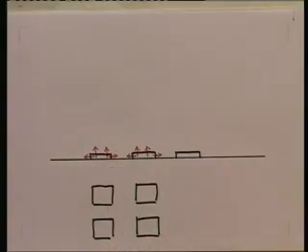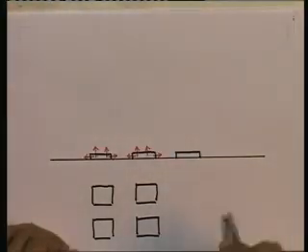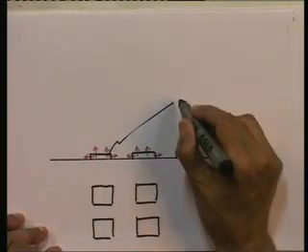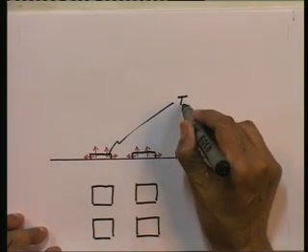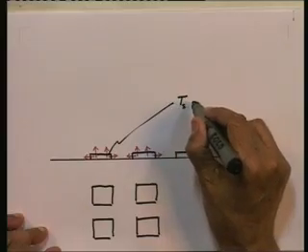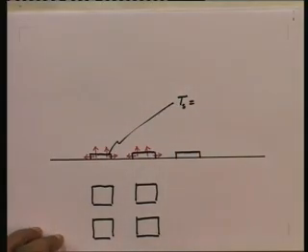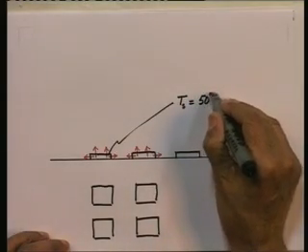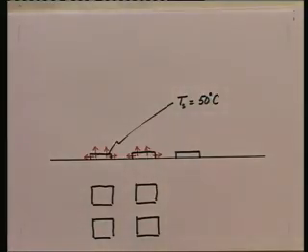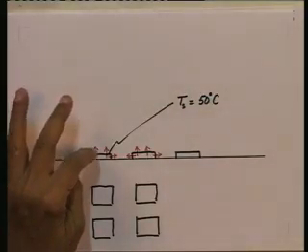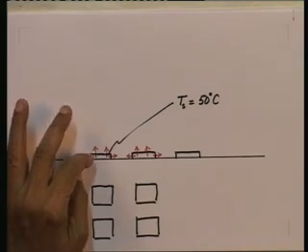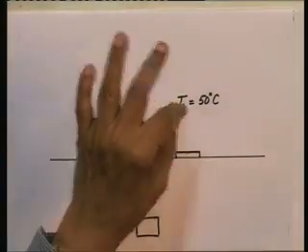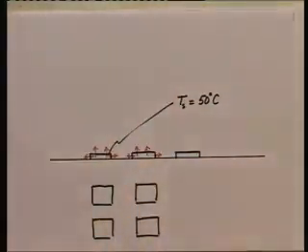The requirement before the heat transfer engineer would be that the surface temperature here, Ts or T wall, whatever we want to call it, should not exceed a value like, say, 50 degrees centigrade or 60 degrees centigrade. That is a typical specification. So, the heat which is flowing out of this will obviously raise the temperature of the surface, but that temperature must never go above a temperature which is specified, typically 50, 60 or something like that.